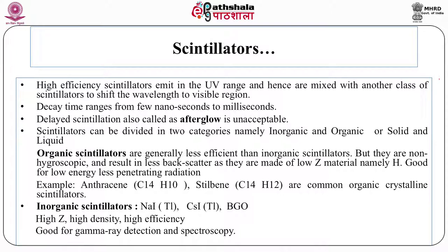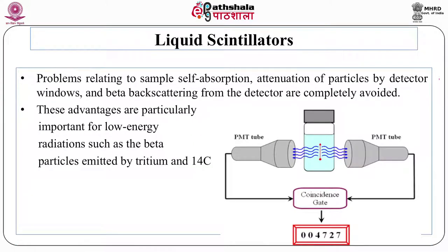These scintillator detectors are good for gamma ray detection and spectroscopy. For liquid scintillators — if there is very low energy radiation such as beta radiation from a certain source, beta radiation may not be able to penetrate into the detector to its sensitive volume. So the radiation-emitting source is mixed with the liquid scintillator, which then emits light that comes out of a transparent container and falls on photomultiplier tubes or photodiodes. Liquid scintillators are particularly advantageous for low-energy radiation such as beta particles emitted by tritium and carbon-14.